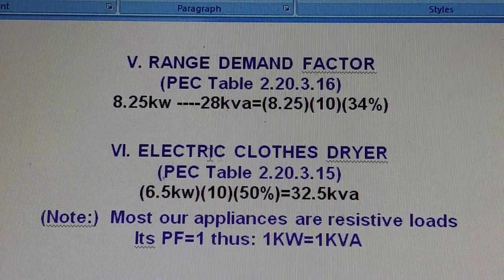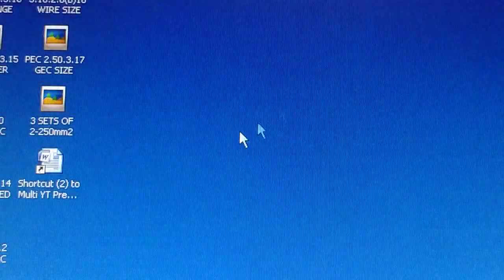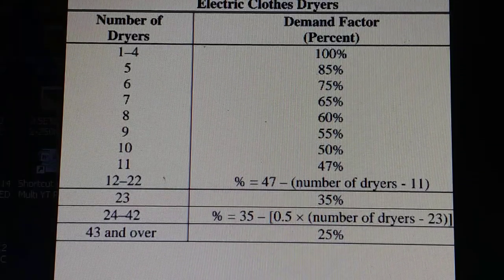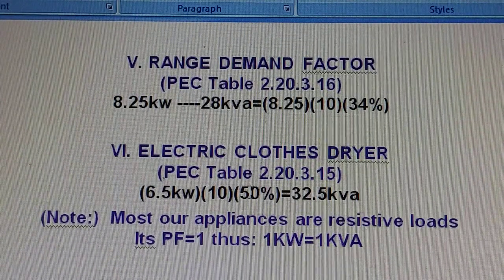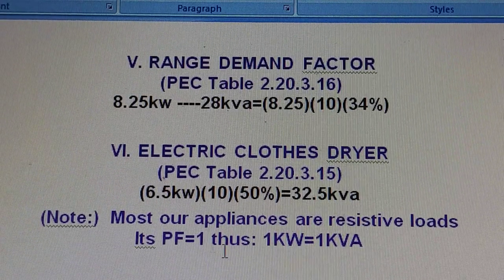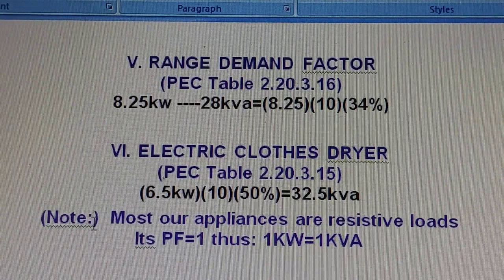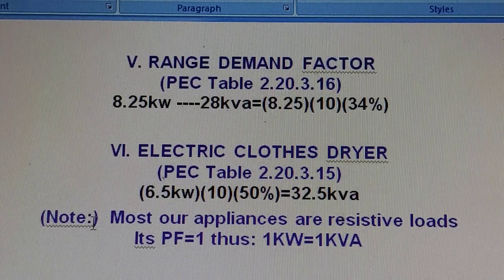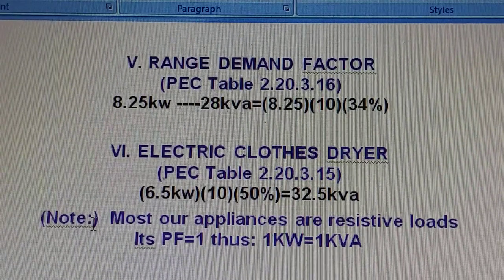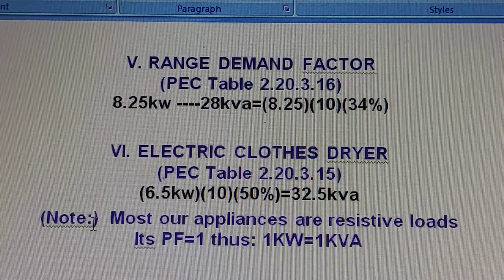For the electric clothes dryer, we get 50% from the dryer demand factor table. With 10 dryers for the 10 condo units, we apply a 50% demand factor. From the table, the calculated value is 6.5 times 10 times 50% which equals 32.5 kVA. Note that most of our appliances here are resistive loads, meaning the power factor equals one, so by rule of thumb, one kilowatt equals one kVA.